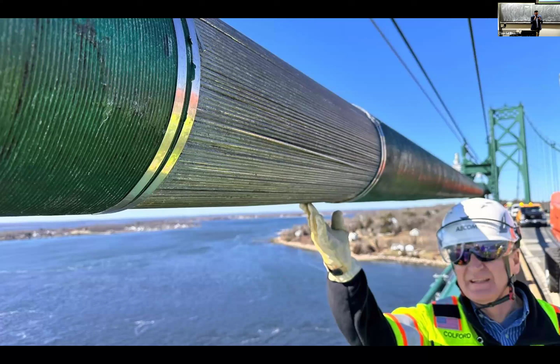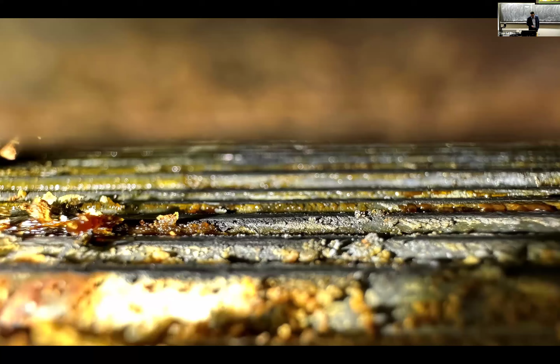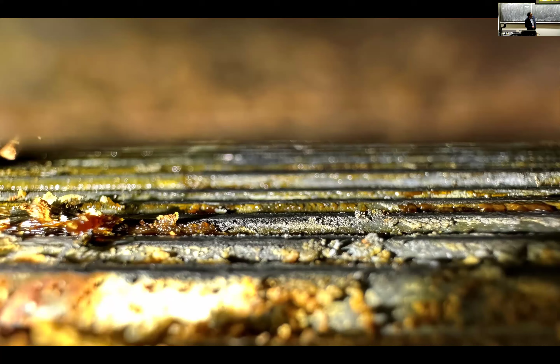You can see during the blow test, this is the airflow testing. This cable is also oiled, which is why we're doing a pretty significant airflow test here. When we started wedging it open, that's what the inside of the cable looks like with the oil.